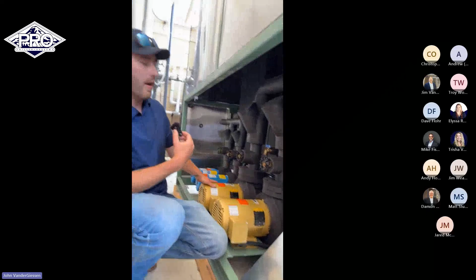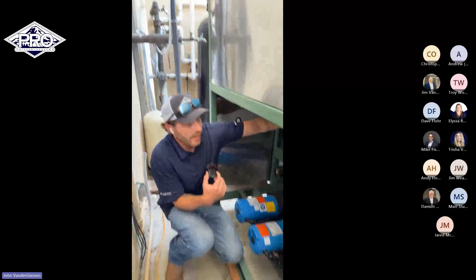Yep, and then by a flip of a switch, you can go to a backup pump. You can bypass the drive by a flip of a switch if you need to. Everything is easily flipped back and forth. Same thing for the circulation pump. These blue pumps here, you have a primary and you have a backup. The primary pump, when there's a call for cooling, it supplies flow to the evaporator and then feeds that chilled glycol back to the tank. If for some reason there's an issue with this pump, flip of a switch, you can swap to the backup and it'll fire right up and take over.